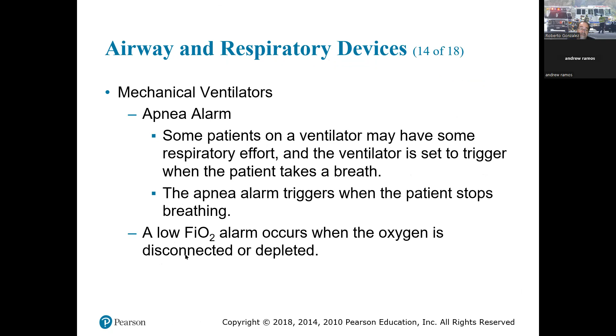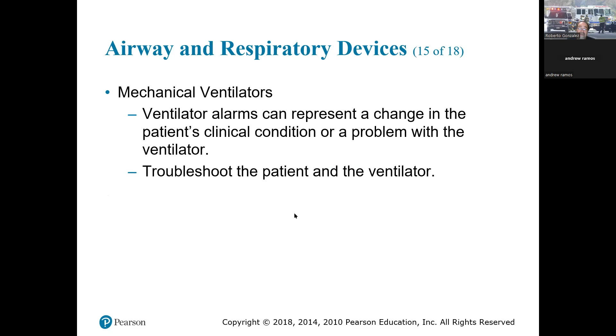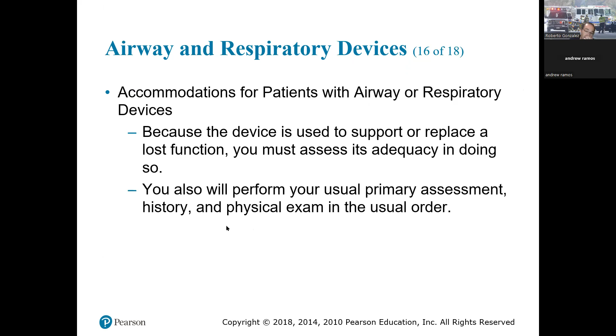Ventilator alarms can actually represent a change in the patient's clinical condition or a problem with the ventilator. Troubleshoot the patient and the ventilator itself. Because the device is used to support or replace a lost function, you must assess its adequacy in doing so. You also will perform your usual primary assessment, history, and physical exam in the usual order. And we're bringing in circulation, remember that.